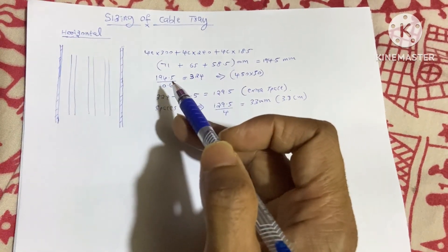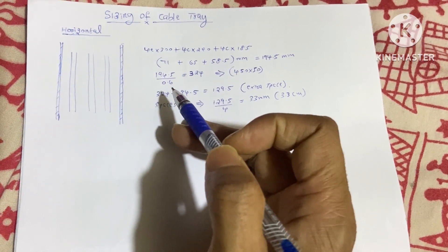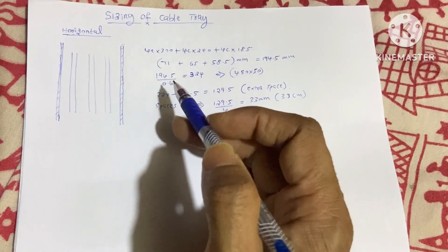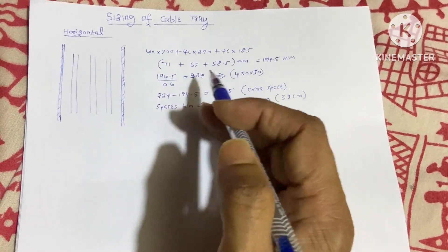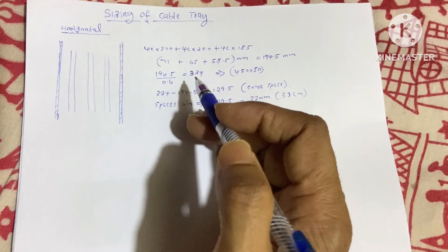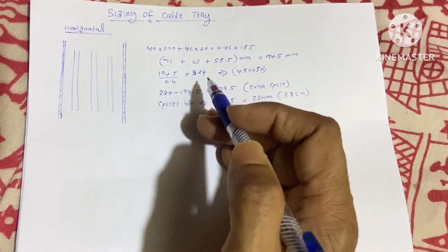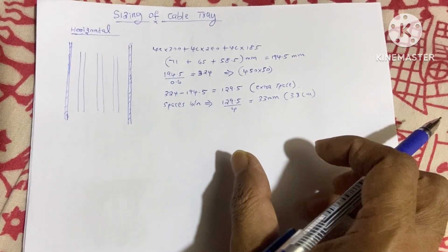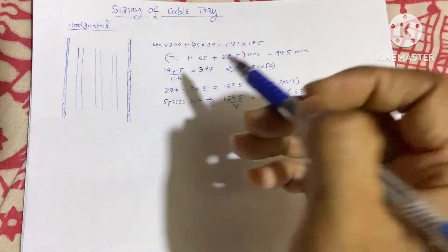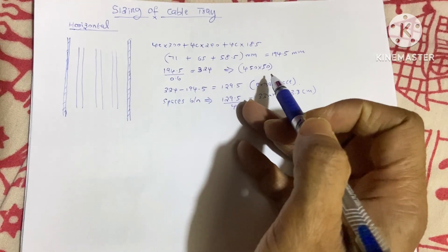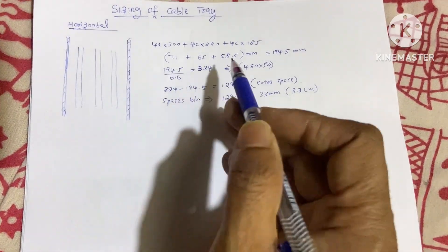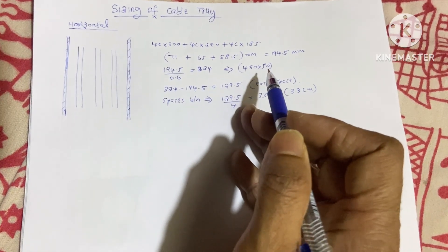To calculate the cable tray size, we apply a safety factor of 60%, so we divide 194.5mm by 0.6 to get 324mm. Since a 324mm cable tray is not available, we select a 450×50mm cable tray, where 450mm is the width and 50mm is the height.